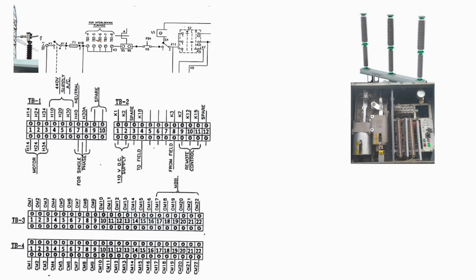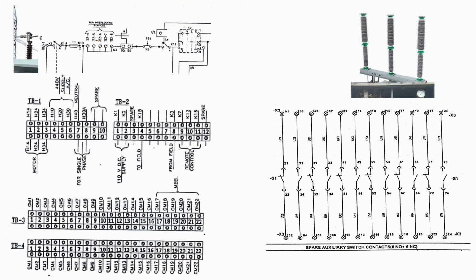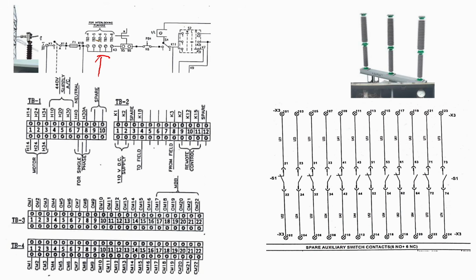In this case what you have to do, you need to use a breaker auxiliary contact here. So for that you need to use this portion. This is the isolator closing interlock. Earlier we had discussed the breaker closing interlock. In this case we are discussing the isolator interlock. So this is the portion where you can make the isolator interlock arrangement.